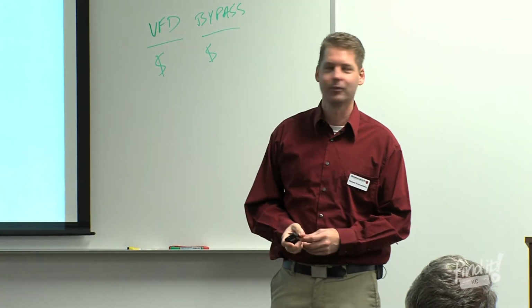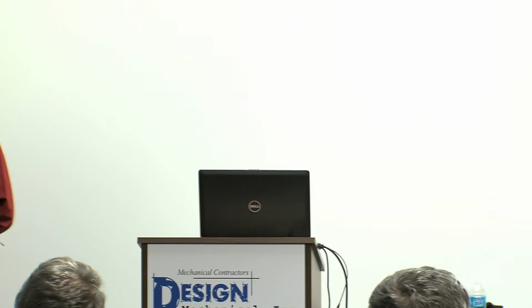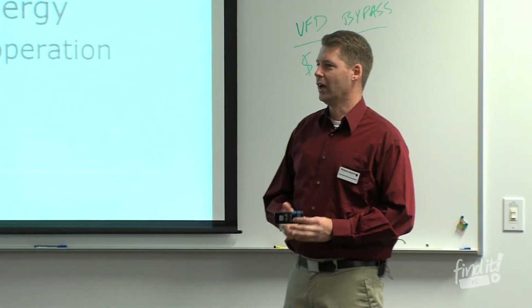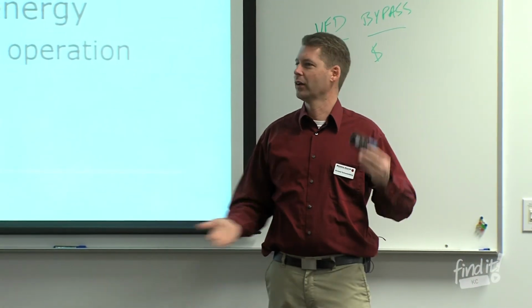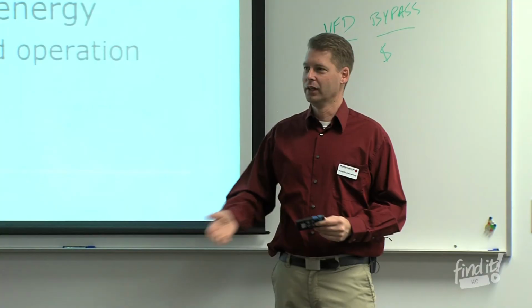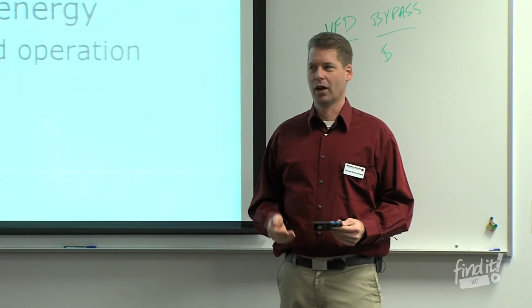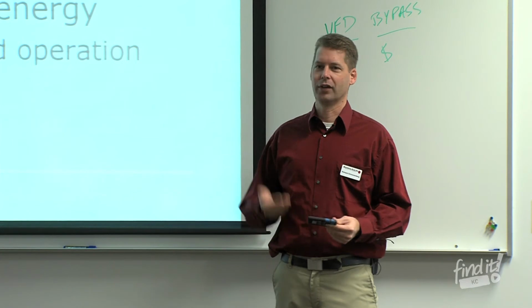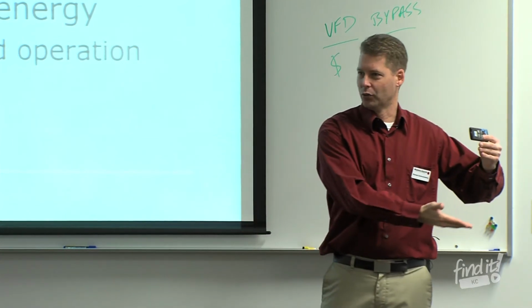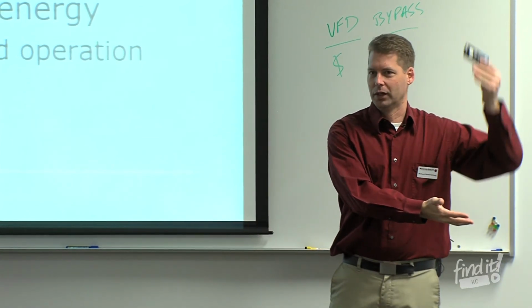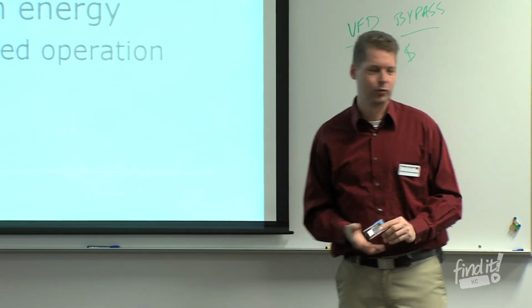Now, Richard, is that based on ASHRAE duty cycle? Yeah, this is an ASHRAE duty cycle of an estimated time of running for an office building, where 23% of the time it's going to run at 60% load, but only 3% of the time is it actually going to run at 100% speed. So there's a time of speed variation that it's based on.